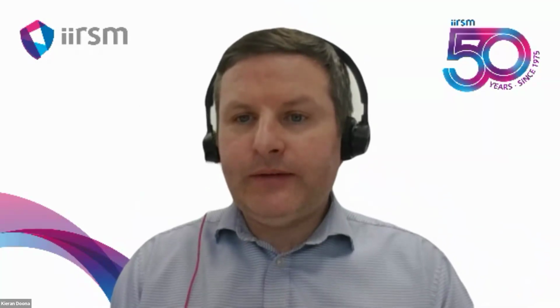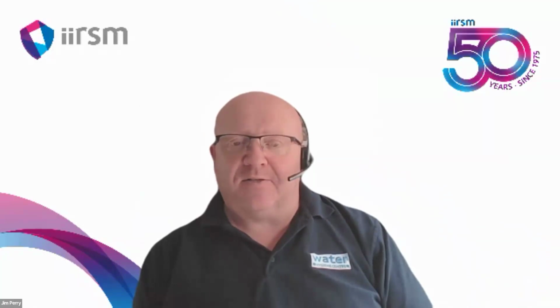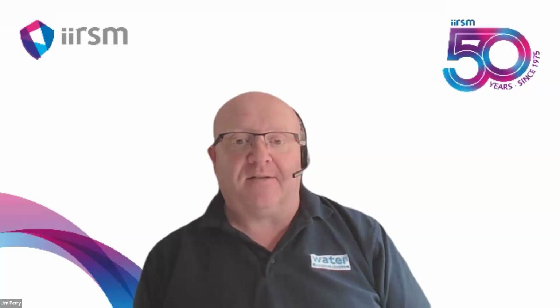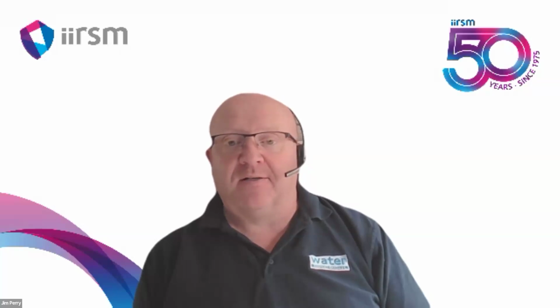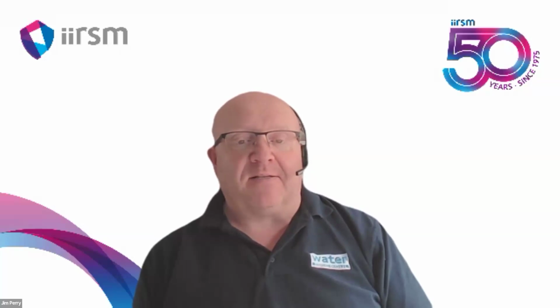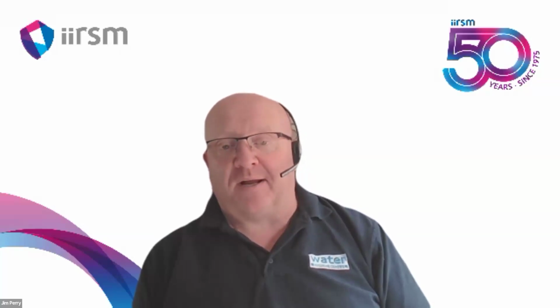Pratima asks: Pseudomonas flushing in augmented care area, is it applicable to all taps or little used outlets? Is it related to the duration of flushing, or is it more to do with water sitting in taps or anything like that? For augmented care settings and pseudomonas flushing, the HTM 04-01 states that we should be flushing all these facilities. That's every tap, toilet, and any other equipment connected to the hot and cold water services, which should be flushed daily.